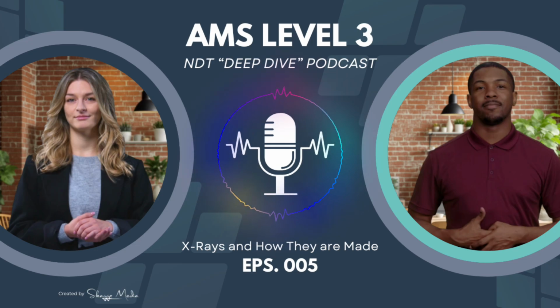Constant potential, does that mean constant energy X-rays? Common misconception. It means the accelerating voltage applied to the electrons is kept very close to its maximum value throughout the whole AC cycle, very little ripple.